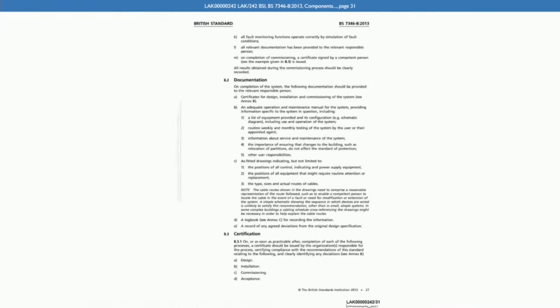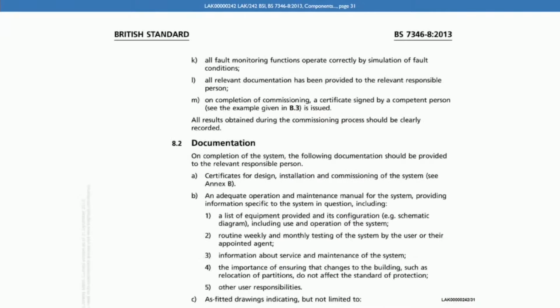If we go to clause 8.1.3 on page 30 of this document, this then lists particular requirements for inspection and testing. So it says at commissioning, the entire system should be inspected and tested to ensure that it operates satisfactorily, and that in particular, and you can see at B, the agreed cause and effect requirements are correctly implemented and the system is tested and responds to any planned method of initiation. I'm not going to read all of them out, but were you familiar with these requirements? Yes, they're amongst the ones that are also required in 12101 Part 6. Yes, I see. And over on page 31, the final requirement listed is for a commissioning certificate signed by a competent person. That's at M at the top of that page.